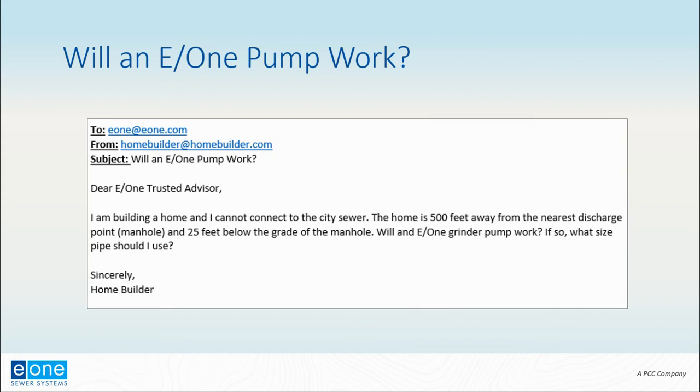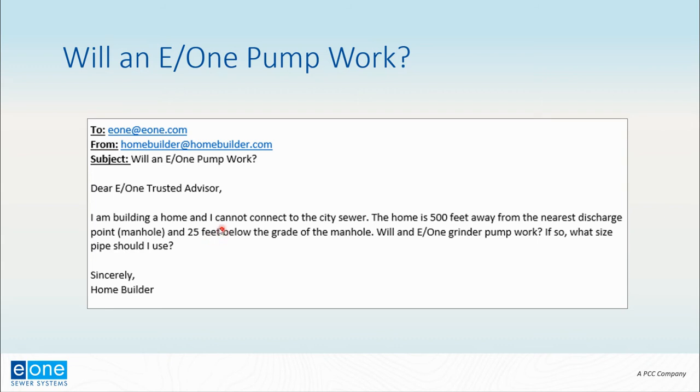Here's an example email: a home builder is building a home and it is too far away from the city sewer. This is actually really common. They know how far they are from the city sewer—500 feet—and that there's an elevation change of 25 feet. They're wondering if an E/One grinder pump station would work for this property and wondering what pipe they should use.